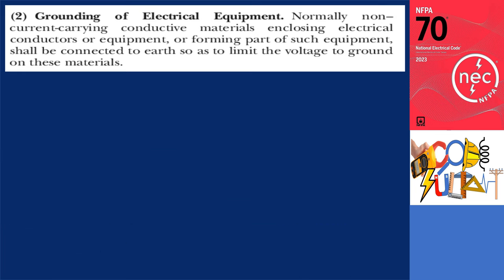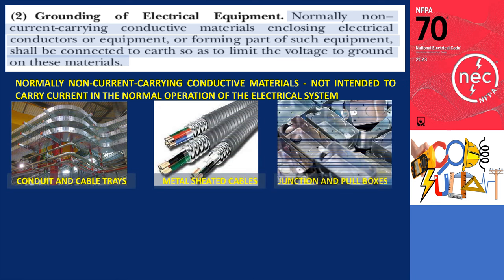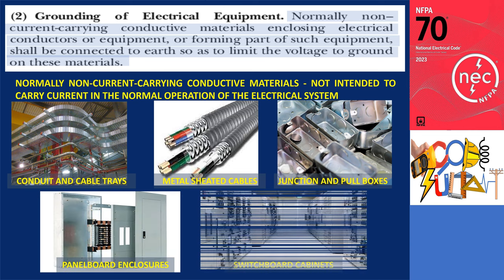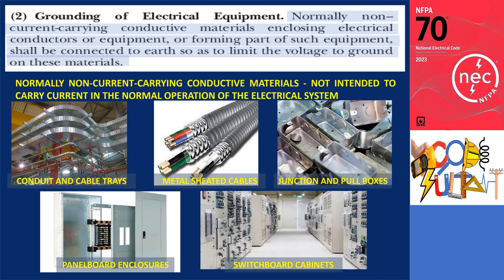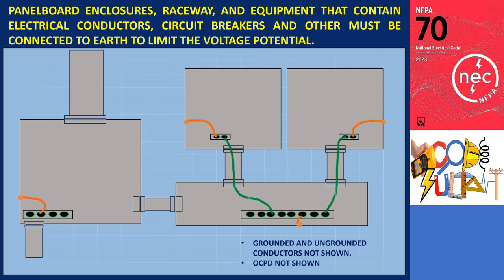Section 250.4A2 — Grounding of Electrical Equipment — states that normally non-current carrying conductive materials enclosing electrical conductors or equipment, or forming part of such equipment, shall be connected to the earth to limit the voltage to ground on these materials. These normally non-current carrying materials include metal conduits, metal-sheathed cables, junction boxes and pull boxes, panelboard enclosures, switchboard cabinets, and cable gutters. Their primary purpose is to provide protection and containment for insulated conductors, overcurrent protective devices, and other electrical accessories.